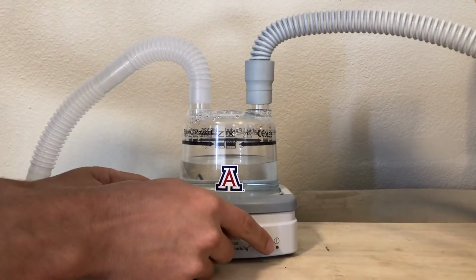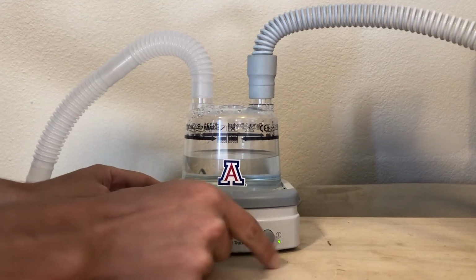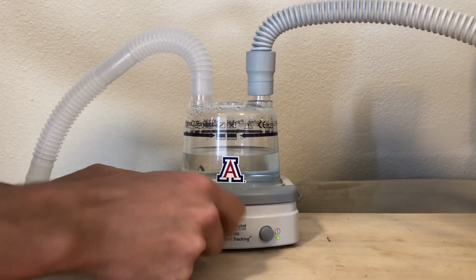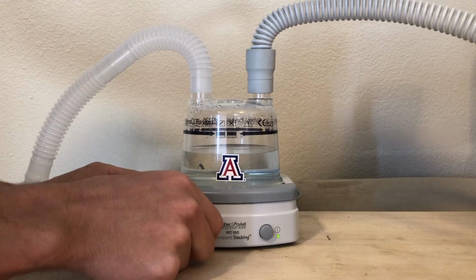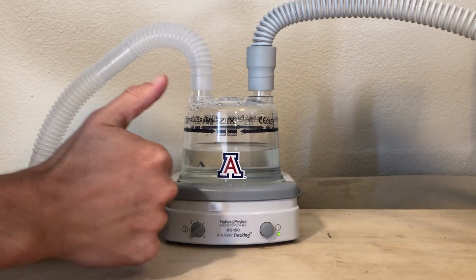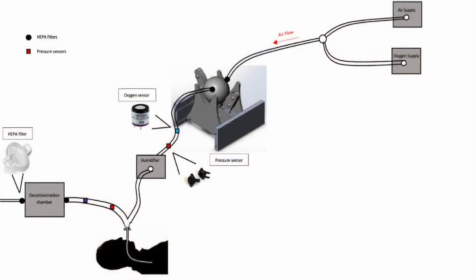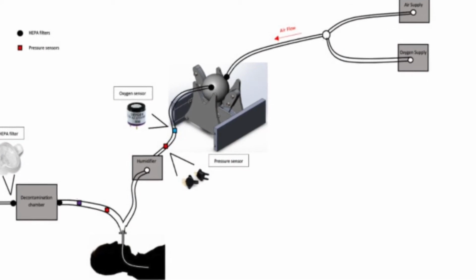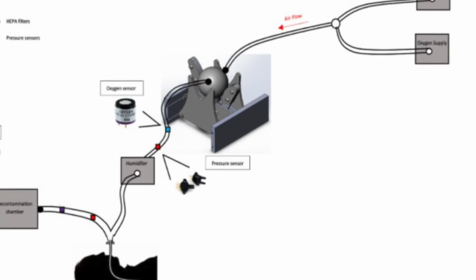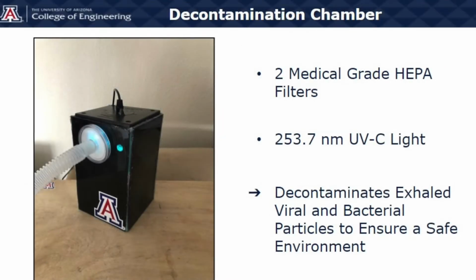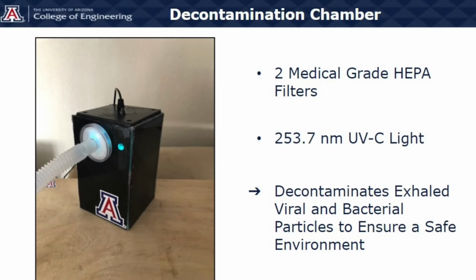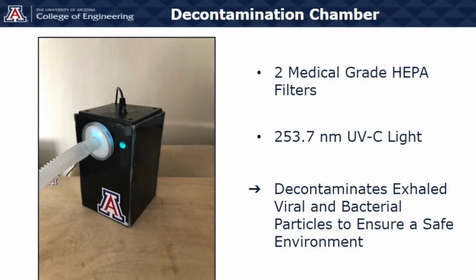Furthermore, we noticed that current designs failed to consider air temperature during inhalation, so we implemented a humidifier in order to add moisture and warmth to the air that is delivered to the patient as they're inhaling. The air exhaled from the patient then travels to the decontamination chamber. The patient has likely exhaled viral particles, so the air needs to be filtered before being released into the atmosphere. The decontamination chamber is designed with two medical-grade HEPA filters, one at the inlet and one at the outlet, and a chamber with the UVC light.